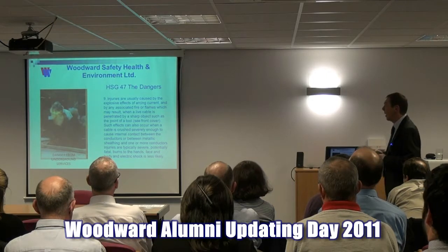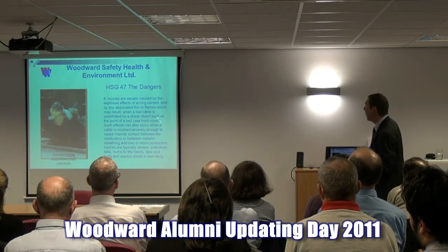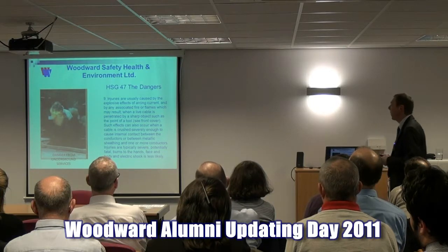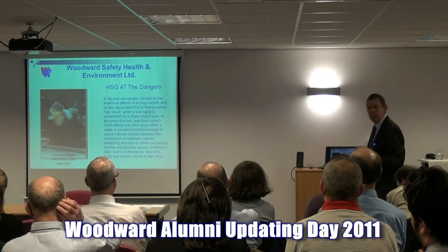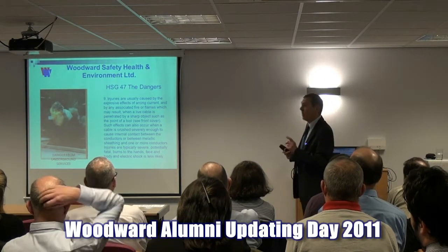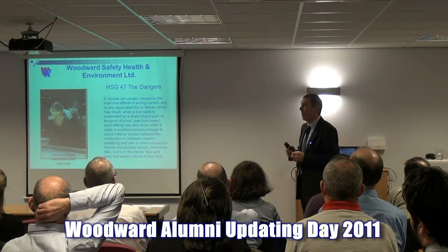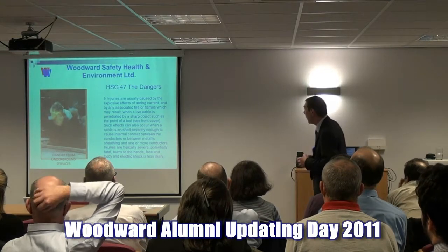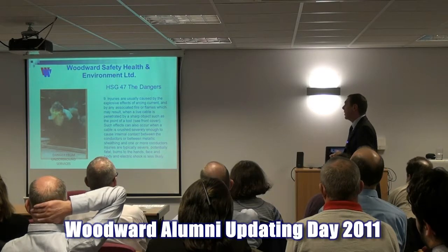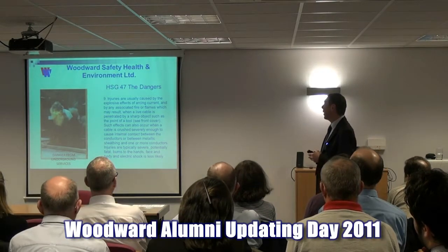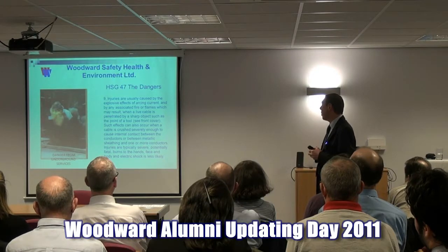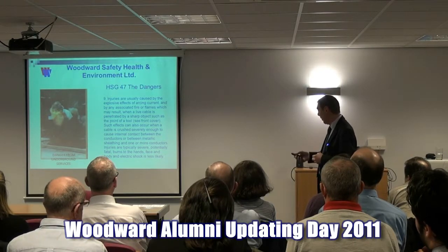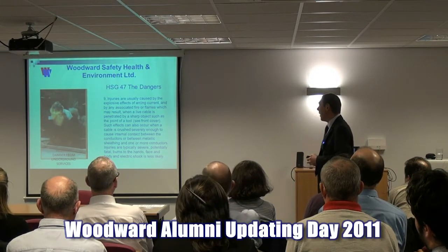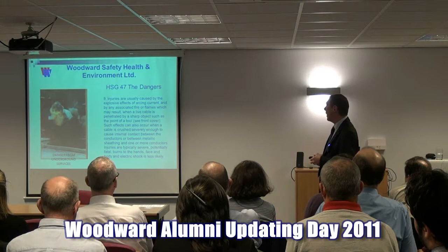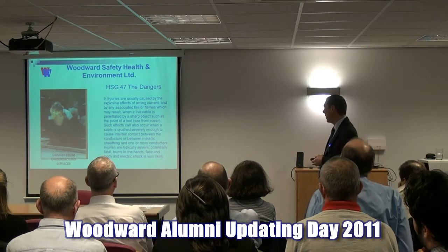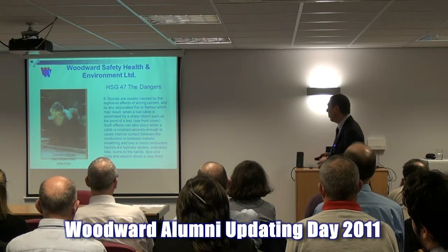We know about these because in this free document, paragraph 9 tells us all about it: injuries are usually caused by the explosive effect. It's electricity - I did start this presentation by telling you it was a source of energy. Yes, electricity can explode. The effects of arcing current and associated fire or flames may result when a live cable is penetrated by a sharp object, such as the point of a tool - as shown on the front cover example. Such effects can also occur when a cable is crushed severely enough to cause internal contact between the conductors, or between metallic sheathing and one or more conductors.